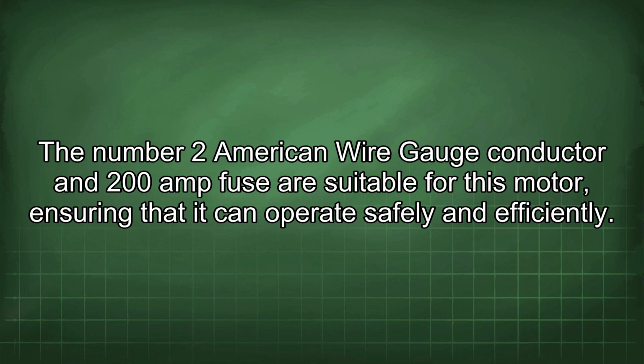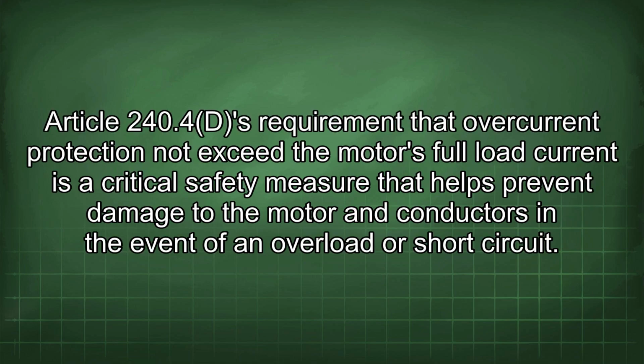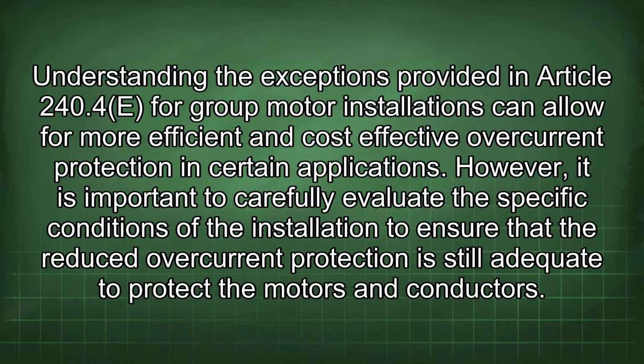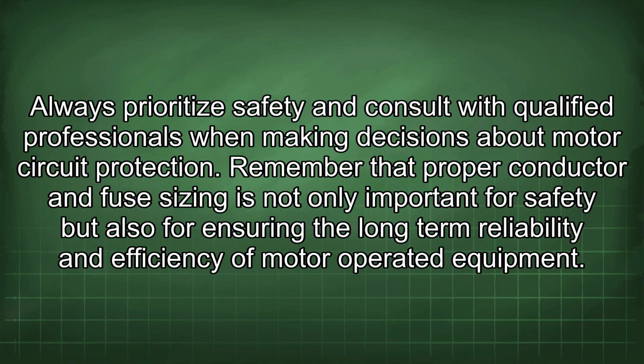Article 240.4d's requirement that overcurrent protection not exceed the motor's full load current is a critical safety measure that helps prevent damage to the motor and conductors in the event of an overload or short circuit. Understanding the exceptions provided in Article 240.4e for group motor installations can allow for more efficient and cost-effective overcurrent protection in certain applications. However, it is important to carefully evaluate the specific conditions of the installation to ensure that the reduced overcurrent protection is still adequate to protect the motors and conductors. Always prioritize safety and consult with qualified professionals when making decisions about motor circuit protection.